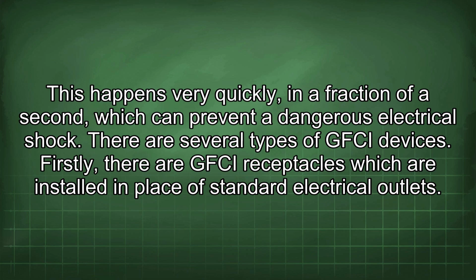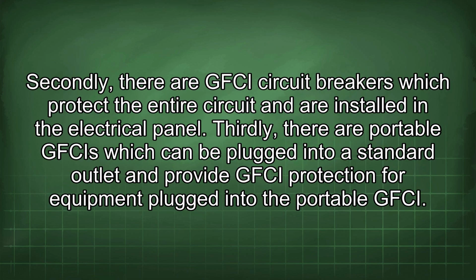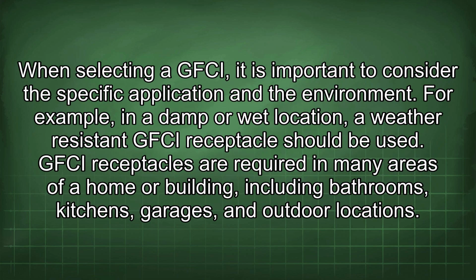There are several types of GFCI devices. Firstly, there are GFCI receptacles, which are installed in place of standard electrical outlets. Secondly, there are GFCI circuit breakers, which protect the entire circuit and are installed in the electrical panel. Thirdly, there are portable GFCIs, which can be plugged into a standard outlet and provide GFCI protection for equipment plugged into the portable GFCI. When selecting a GFCI, it is important to consider the specific application and the environment.